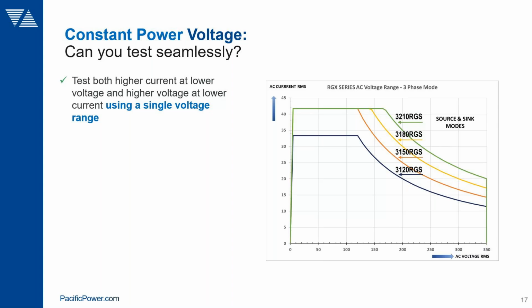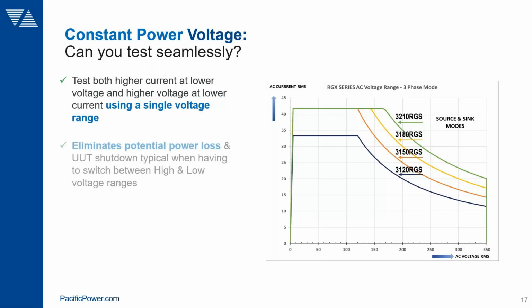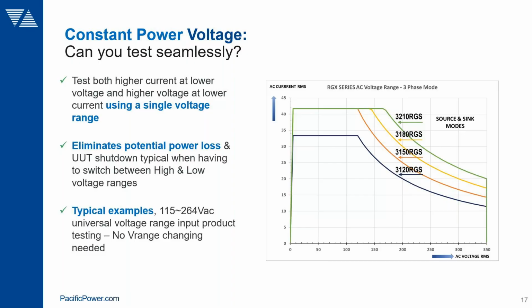So the constant power voltage range does not do that, so you can stay on the same range. That's definitely a benefit, as you can do those wide range products, for example, that run from 120 volts AC to 264 volts AC, and you can test them smoothly over the entire range without having to deal with switching ranges. So that's a typical example.